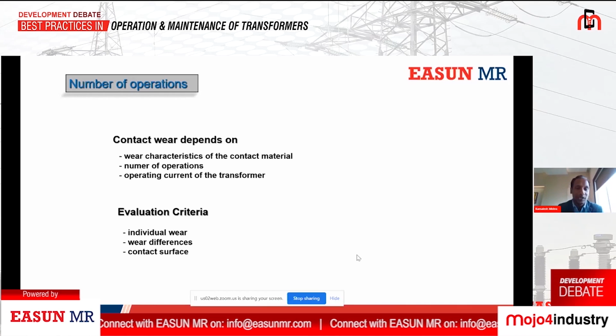You can see here totally black. So by that, what happens? There are two things. One, the oil gets black, which means the BDV of the oil basically reduced, which means insulation also reduced. Another one, you have a lot of material from the contacts, which is basically deposited. So in between your contacts or below the diverter switch, that has to be removed. How will it be removed?